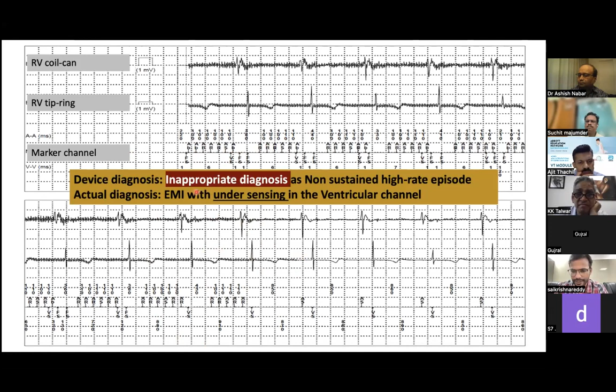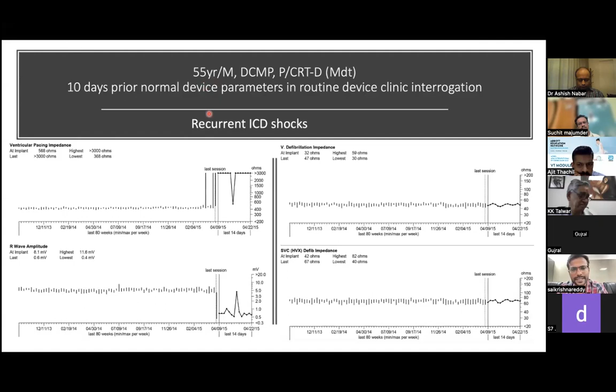So this is another case of a 55-year-old male who had DCMP and underwent a CRT-D implant. He came to our clinic 10 days prior, when interrogation was normal. Then after 10 days, he presented to the emergency with multiple ICD shocks. This example shows the significant importance of lead parameter trend analysis. On the left, the upper channel is ventricular pacing impedance and the lower is R wave amplitude, and on the right side the upper and lower are defib impedance and SVC coil impedance respectively.